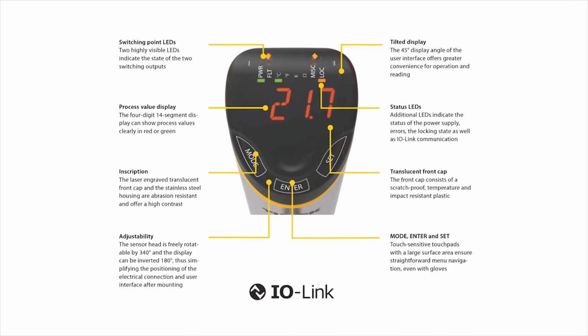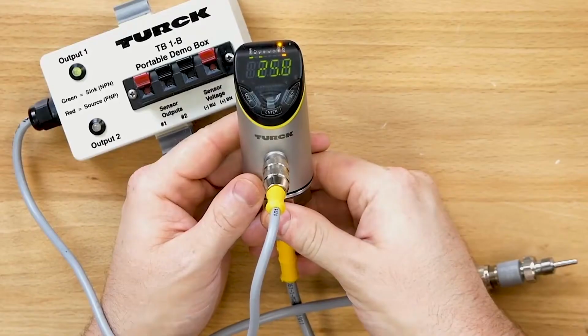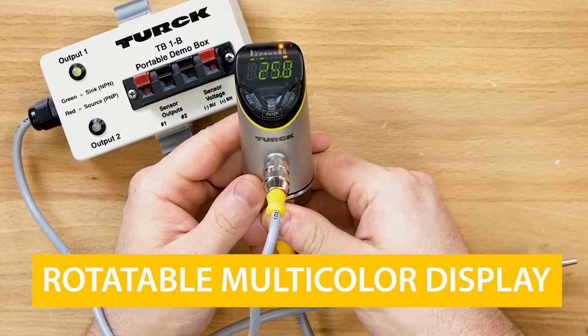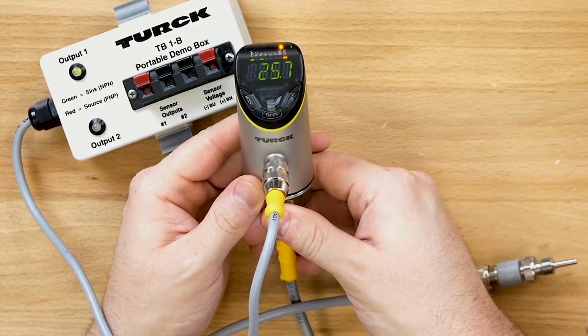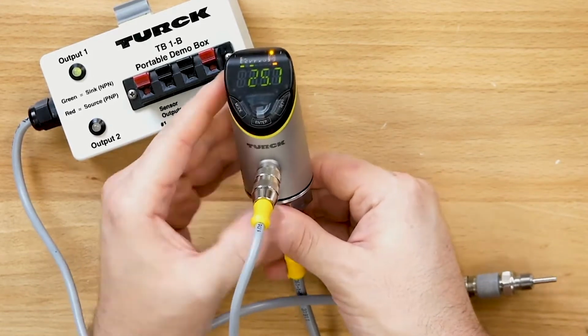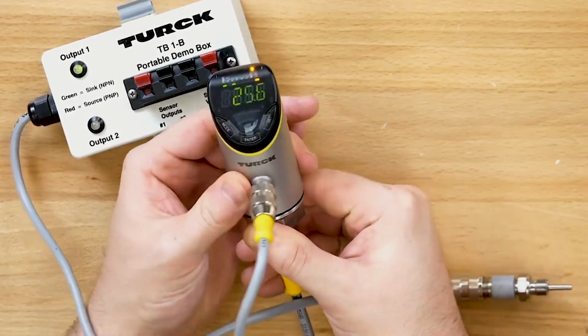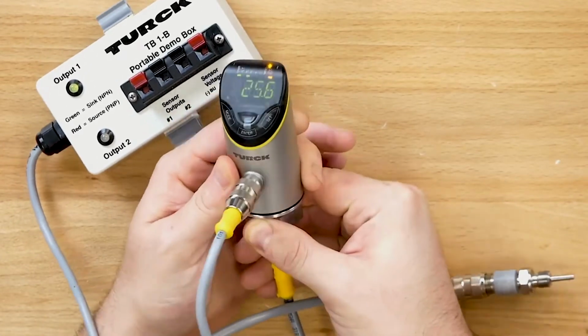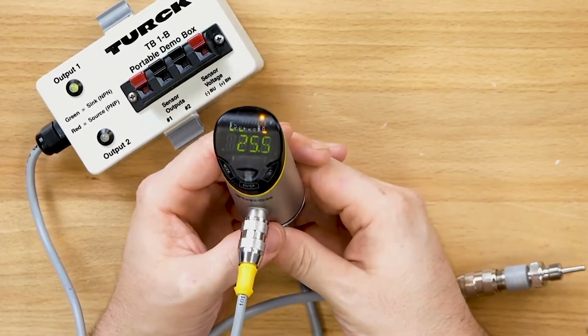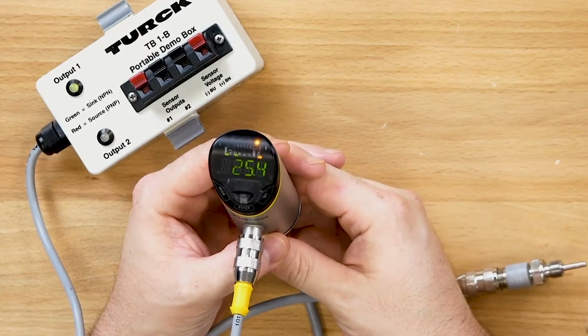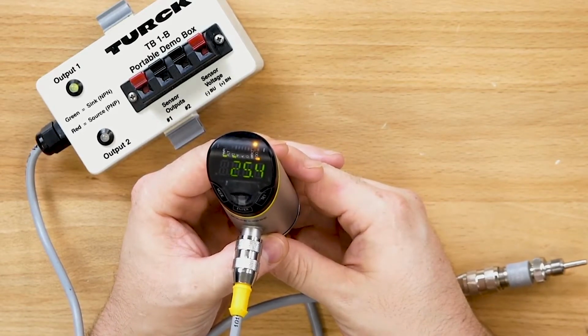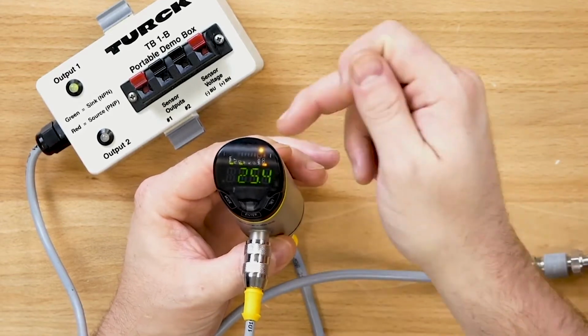The TS Plus includes a number of enhancements over the previous TS400-500 families. The design also mirrors the PS Plus pressure sensors and the FS Plus flow sensors for ease of use. The TS Plus has a sloped, rotatable, multicolor display that simplifies installation and commissioning. Note how easy it is to rotate the top of the sensor to achieve the optimal viewing angle. In addition, monitoring the output state is designed with visibility in mind. If a program switch point is exceeded, the sensor will show a visual indication here or here.